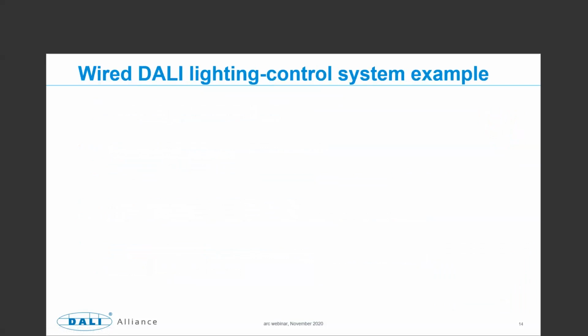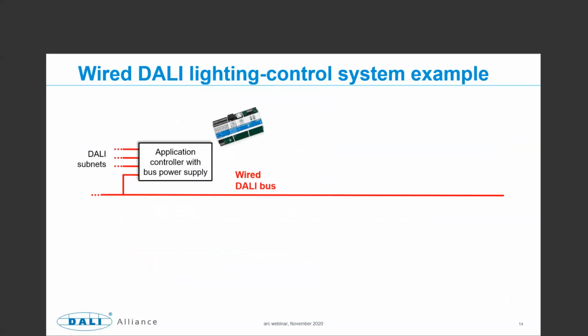So, a wired DALI lighting control system example, and we'll build up this example stage by stage. To start with, we have an application controller, and in this example, it has the bus power supply built in, and it connects to the DALI bus, our 2-wire bus. And this application controller might have other DALI subnets, so other DALI buses. So these are separate DALI systems, all accessible from the same application controller. And we'll just look at one of these DALI systems here, one subnet.